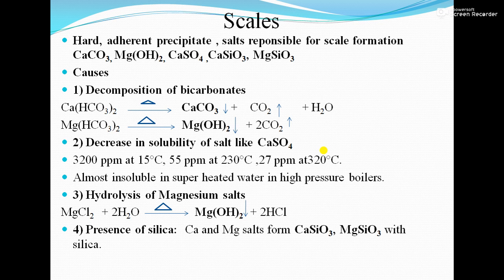At 320°C solubility drops further to 27 PPM — calcium sulfate is almost insoluble in superheated water in a high-pressure boiler. As temperature increases, solubility of calcium sulfate decreases. The third cause is hydrolysis of magnesium salts: magnesium salt in water reacts at higher temperature to produce magnesium hydroxide. Fourth, the presence of silica — calcium and magnesium salts react with silica to form calcium silicate and magnesium silicate, which are insoluble and adhere to the boiler metal.